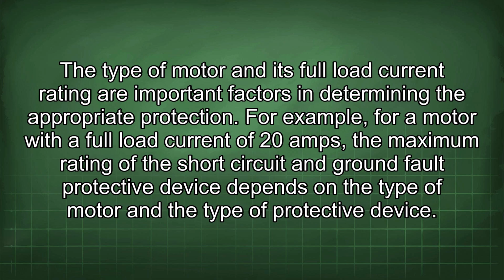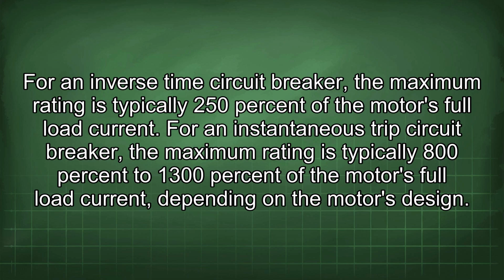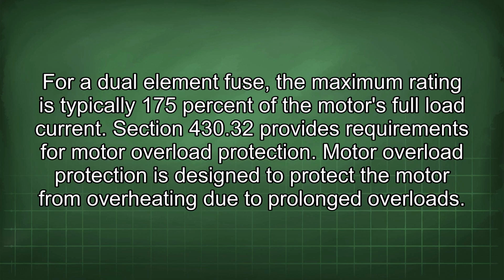For example, for a motor with a full load current of 20 amps, the maximum rating of the short circuit and ground fault protective device depends on the type of motor and the type of protective device. For an inverse time circuit breaker, the maximum rating is typically 250% of the motor's full load current. For an instantaneous trip circuit breaker, the maximum rating is typically 800% to 1300% of the motor's full load current, depending on the motor's design. For a dual element fuse, the maximum rating is typically 175% of the motor's full load current.